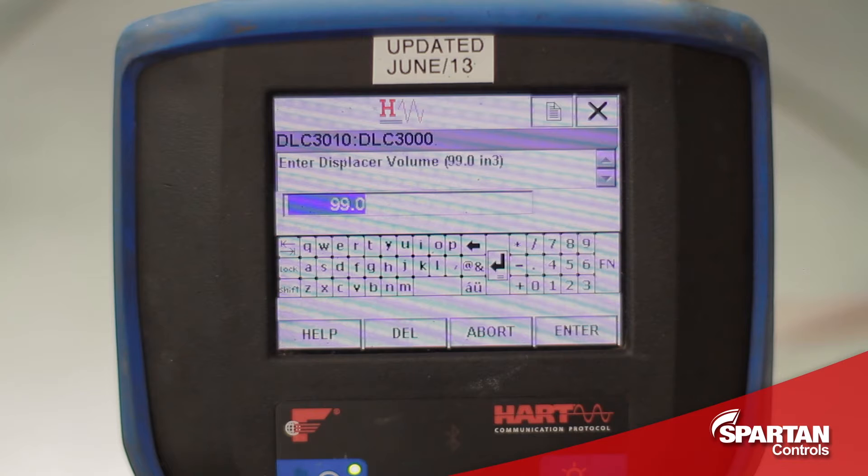The standard volume of a Fisher displacer is 99 cubic inches, but again it is always a good idea to double check your nameplate, just to make sure. The displacer length can also be found on the nameplate, and in this case it is 14 inches.